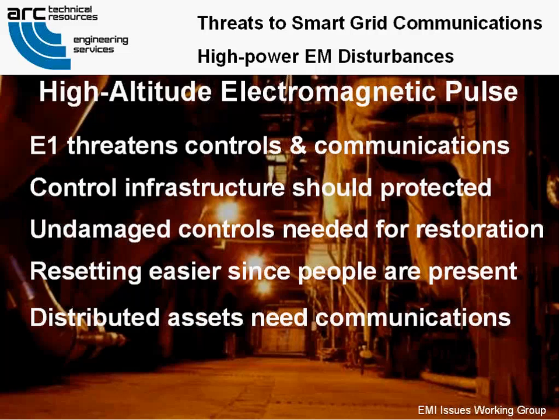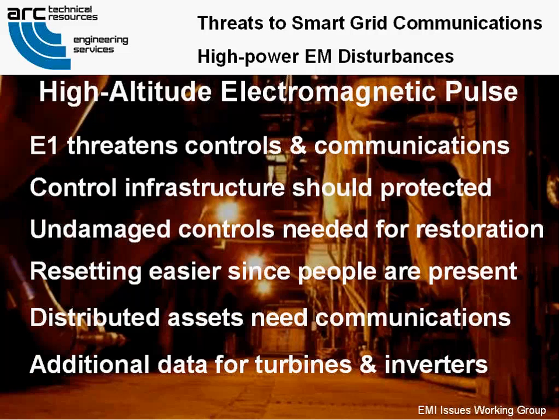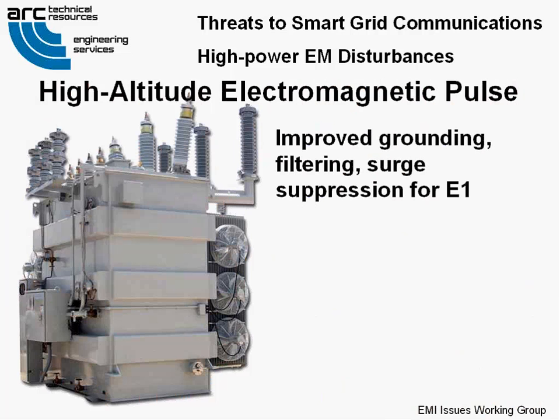For distributed generation, the variability of renewables drives the need for functional communications links to keep generation and loads in balance. Both wind and solar installations will be exposed to E1 HEMP fields, but additional test data are needed to determine if the wind turbines and inverters themselves can survive the effects of a burst. My initial reaction from doing some work on the wind turbines in Illinois is that they won't. Poor immunity. For E1 high-frequency HEMP, improved high-frequency grounding, filtering, and surge suppression are the mitigations.